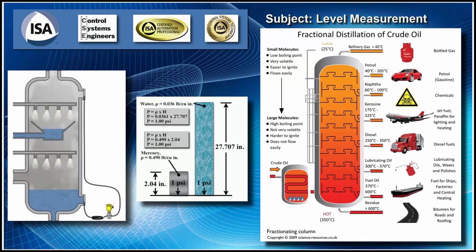If it's heavier than water, we use more inches of water. So we get an equivalent height, whether it's lighter than water or heavier than water. We want to get the actual height. So gasoline would be a smaller column because it's lighter, and something like asphalt or the silicone fill would have a specific gravity of 1.1. So it'd be a taller column of water.